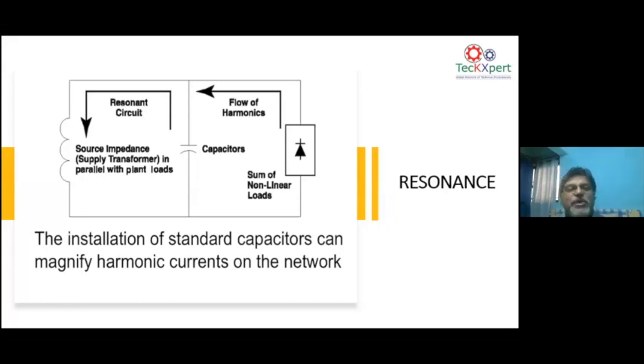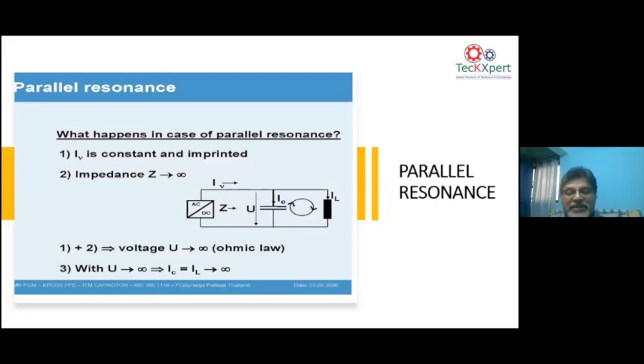But in reality, you don't get infinite current because the network has enough resistance to arrest the rise of current. There are also other impedances, leakage impedances, all that, which will not allow the current to go up substantially. So this is the same as what I told you before. In parallel resonance you have two problems. One is that your voltage goes up substantially and your current also goes up substantially.